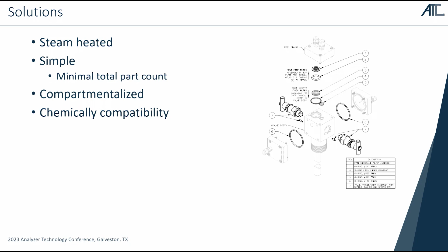Okay, so here's a cutaway of what I was showing, to give you a better idea of what's going on in the belly of the beast. Starting at the pipe, the sample is drawn up through the probe. The sample passes through the isolation valves and the probe body on its way to the sample conditioning system and analyzer. The aspirator driven return sample then moves back down through the tap point.